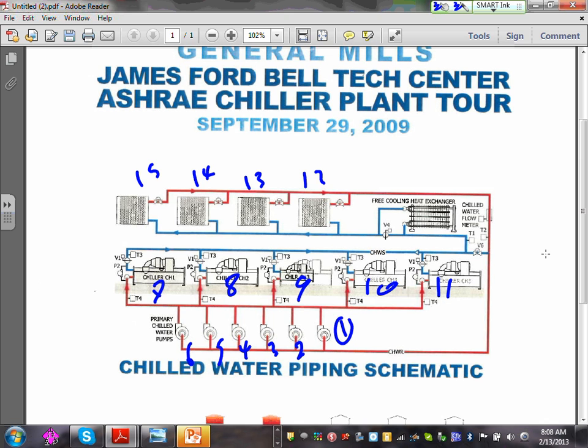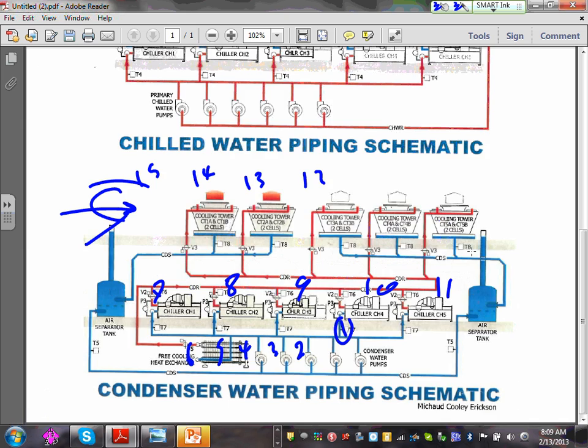And what they're not showing here is that big blower that blows the air right through it and takes it through the ducts to chill that particular area. They have dampers to control the flow of air. This is the flow of water. Right there, the handling unit changes the flow of water into a flow of air, and then you start using dampers to control that flow of air. Any comments, any questions? I want you guys not to leave here not knowing this at least. Any comments, any questions?